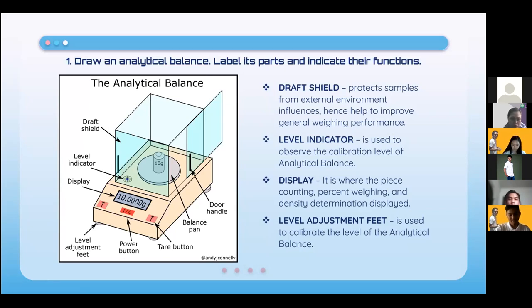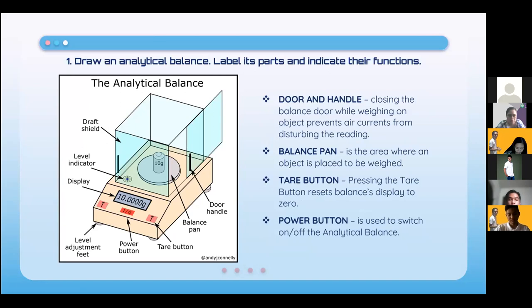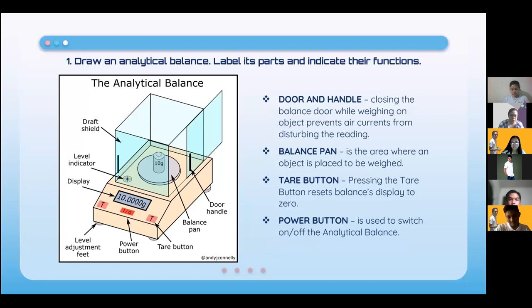In our analytical balance, we have eight parts: the draft shield, level indicator, display, level adjustment feet, door handle, balance pan, tare button, and power button. The draft shield protects samples from external environmental influences such as air or dust, improving weighing performance. The level indicator is used to observe the calibration level of the analytical balance.